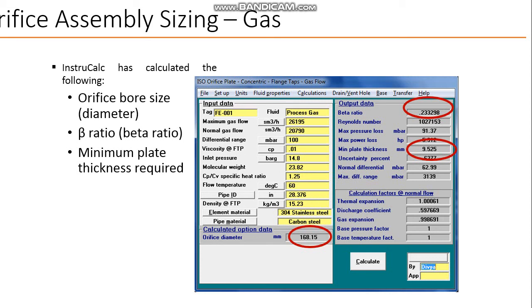As soon as you click on calculate, you can see orifice diameter has been calculated. In millimeters, it is 168.15. Beta ratio is 0.233298, and plate thickness has been calculated as 9.525.